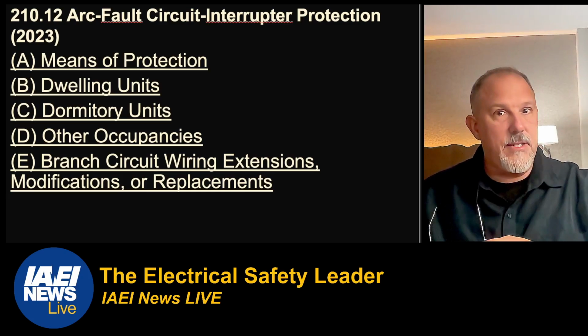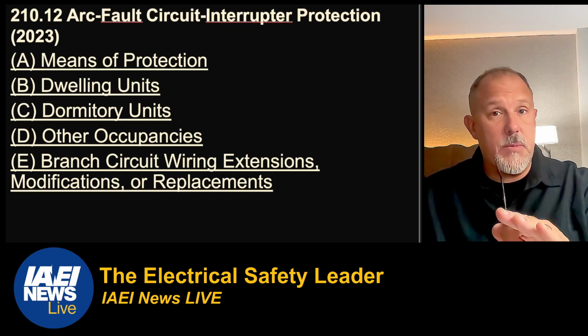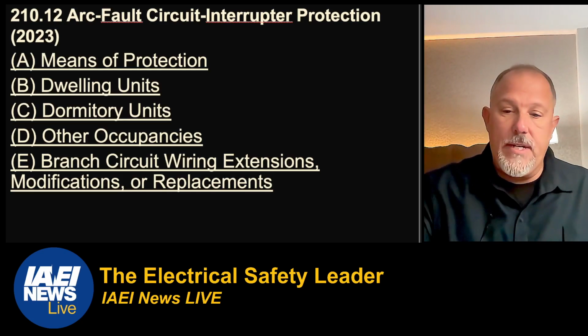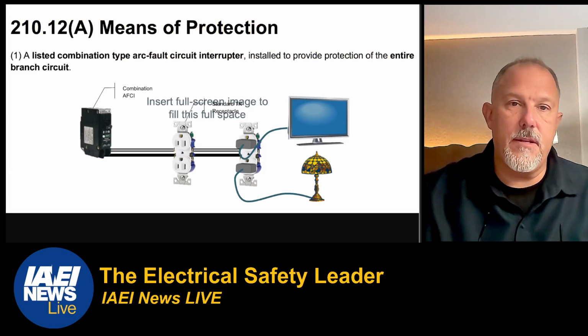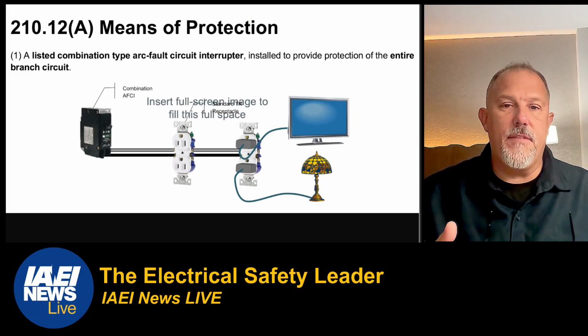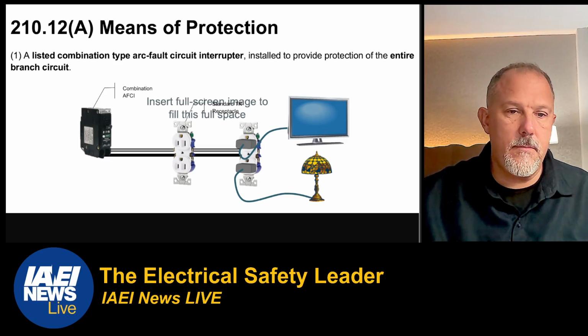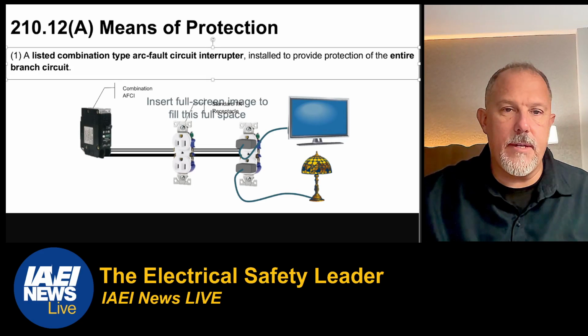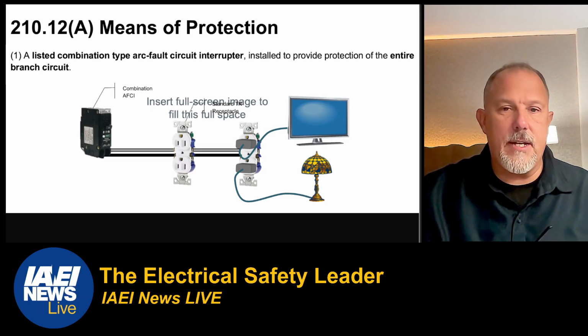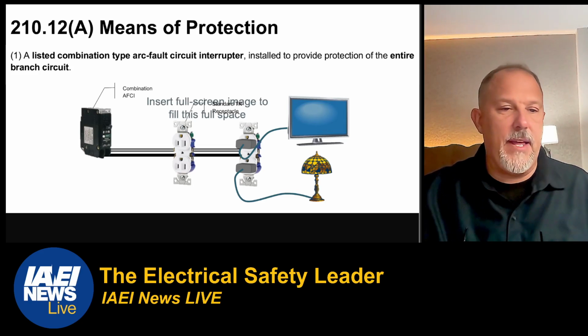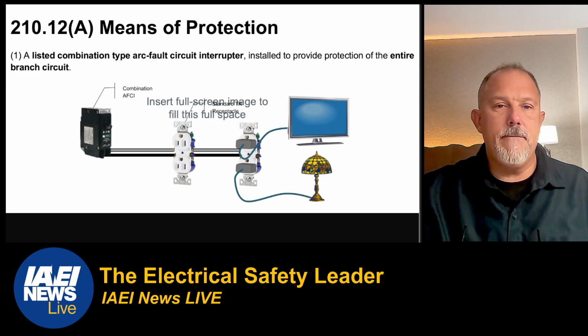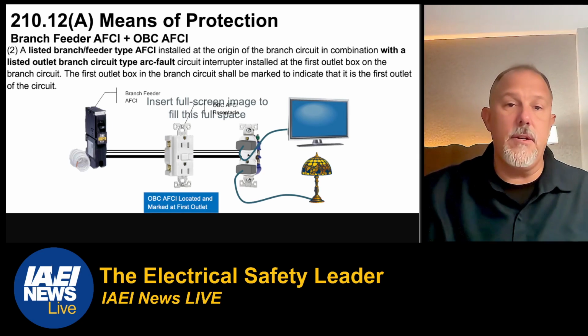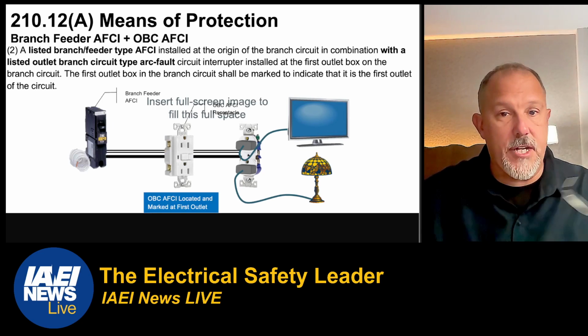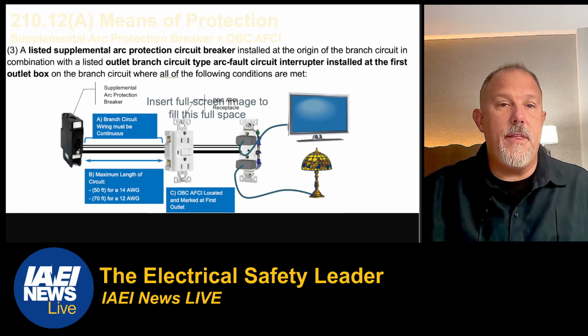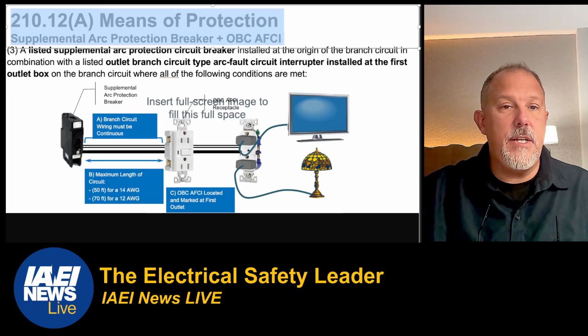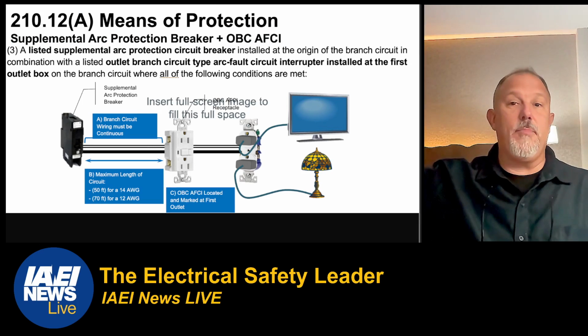So we reorganized 210.12 a little bit. We did do some expansion, I'll cover that, but we did not address the means of protection. So you have the first means of protection. I don't know why that right there is there, but in any case, the first is the listed combination type AFCI at the source of the branch circuit. The second one is a branch feeder plus an OBC AFCI, so you're ensuring the protection of the home run circuit. And then the third option is the supplemental arc protection breaker plus an OBC AFCI.